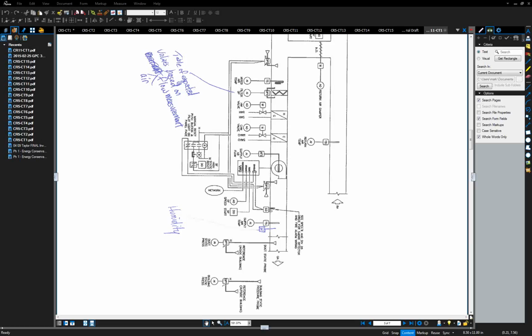Yeah, the other thing you can do is usually when you're first starting up the fans, at some point you're going to full throttle, certainly like on a morning warm-up, for instance. And you could also filter the alarm for that condition where the fan is at or near its full design speed. Then you look at the condition. You enable the alarm per filter. So there's different ways of doing it. Yep. And whichever way is the most efficient and easy to set up, that's what would be nice to have added into this desired sequence of operation.